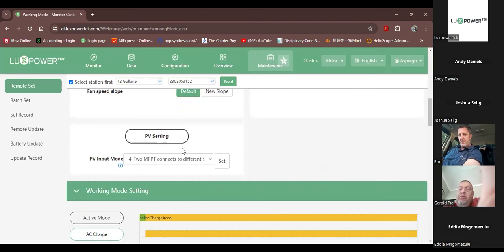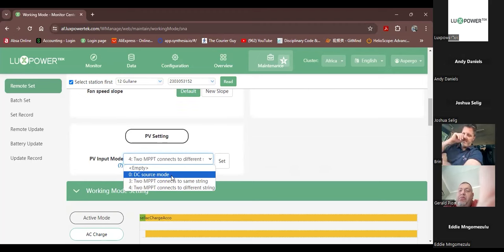Okay, PV setting, here we can obviously set them to a number of settings. This one, if you guys ever see this one here, DC source mode. DC source mode is what we use here in the workshop when we are testing machines, because we've got DC generators or power generators for when we test the MPPTs. So we can set the MPPT voltage range as well as the current. And when we're doing that, we select the DC source mode because there's no fluctuation here. So the tracker can't track anything because the DC power is stable.